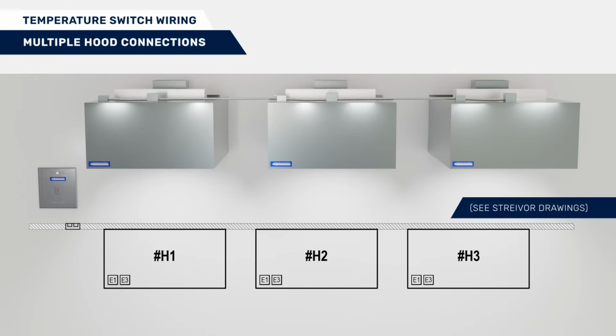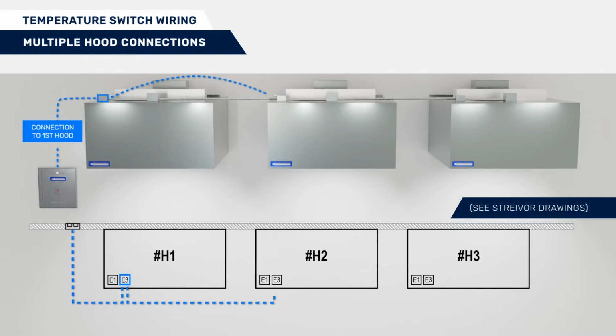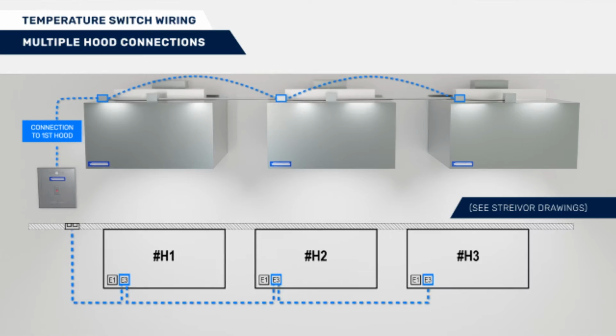The temperature switches can be easily connected between hoods for installations where multiple hoods are interlocked together. After the first hood is connected to the manual switch or DemandAire panel, simply connect the wires from the E3 junction box on the first hood to the E3 junction box on the next hood, and so forth until the temperature switches on all your hoods have been connected. See the Streivor drawings for additional details.